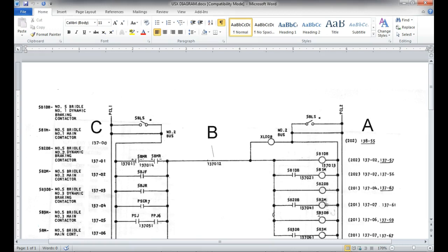So notice, this would be a rung, and this would be a parallel circuit, right? I say that because we have multiple loads or multiple coils, but they're in their own line, right? Makes sense? Every line that lines up horizontally gets the same number. So this is line number 1, and the 137 is the page number on the drawing. Line number 2. Notice the line started what? 0, 1, 2, 3, 4, 5. So they're numbered sequentially right down the page.